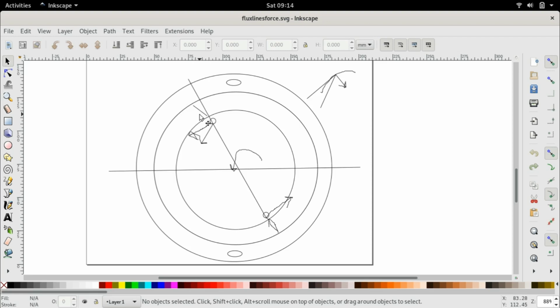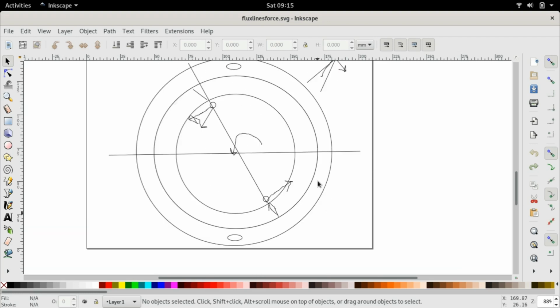There will be undercurrents, there will be other stuff, and in the same way with the magnetic field, there will always be some amount of non-linearity, even though the magnetic field is largely uniform, even if it is designed in such a manner. These non-ideal lines of magnetic force will result in a mechanical force which is not tangential to the rotor, and therefore we can break it down into two projections, one along the tangent and one along the radius. The one along the tangent will continue to produce a rotational torque, whereas the one along the radius will result in vibrations.